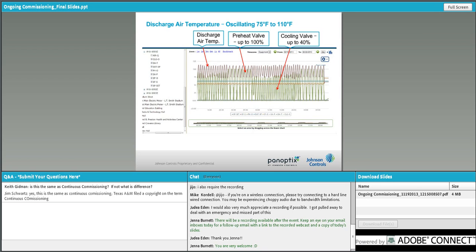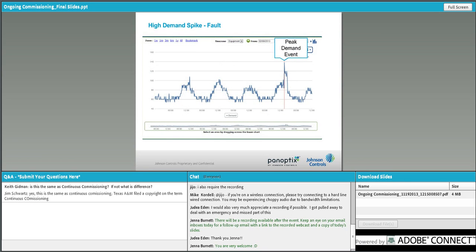Again, detecting it is much easier. This final shot just shows a peak demand. We all understand how important reducing and minimizing demand charges can be. Demand response has really taken off in the last three to five years. This shot shows that the peak demand is usually running right around 100 kW, but something happened this time that peaked it up. If you take an average between 120 and 140, about 130 kW, some activity occurred here to increase that demand by 30 kW.